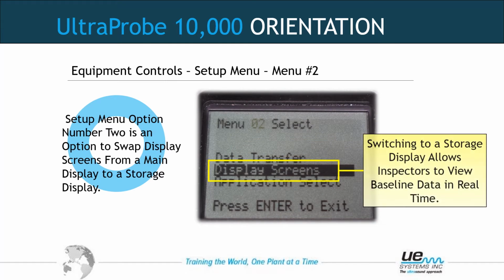Rotate your sensitivity dial to the right one time and you'll come to menu number 2, display screens. We can switch between the storage display, which we'll see later, as well as the main display that we first started working on, as well as a third display that shows up for valves called the ABCD display. It only shows up when the valve application is chosen. It will give you 4 areas, A, B, C, and D, to store a decibel on.